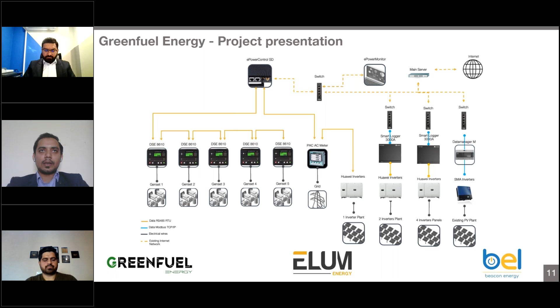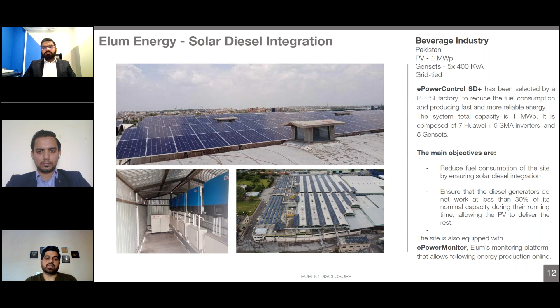So basically, if we talk specifically about the project, as the gentlemen have explained, collectively it's a 1 megawatt project with 5 gensets of 400 kVA each. So we have 2 types of inverter brands to tackle: 7 inverters from Huawei and 5 from SMA. The main purpose here was to reduce the fuel consumption of the site by ensuring solar diesel integration, then ensure the minimum genset loading of 30%, so we can deliver the rest of the power. This site is also equipped with our ePowerMonitor Pro, so the customer can see online how the project is working, what they have generated today, yesterday, or in the last month.